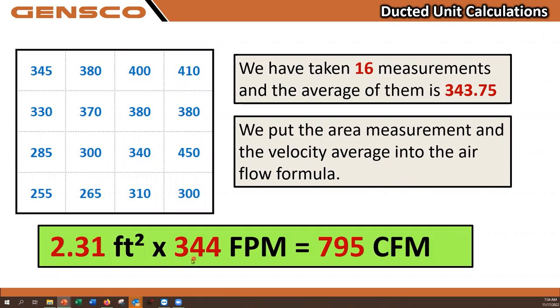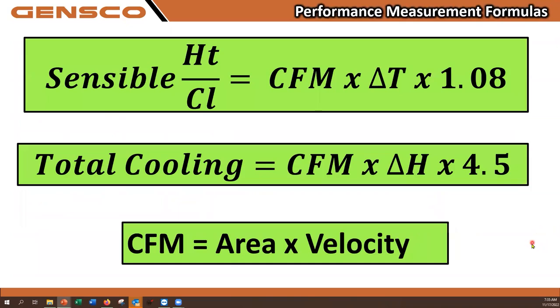2.31 square feet times 344 feet per minute. I am pulling 795 CFM through that grill. There is a little more work involved to do an actual BTU calc on an air handler, because you have this extra step of figuring out how much CFM you actually have. But that is the way to do it. So if you want to take a picture of this as an example, here are the formulas again, if you want to take a picture of them all together.